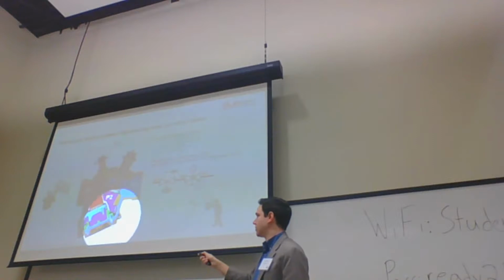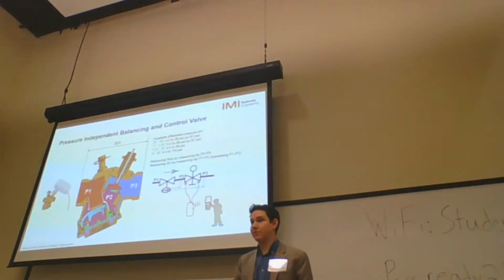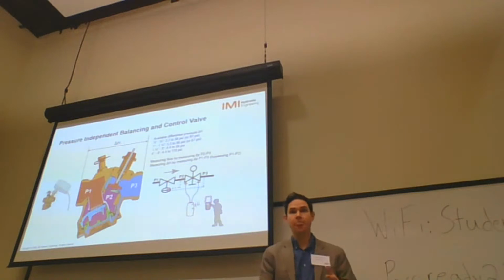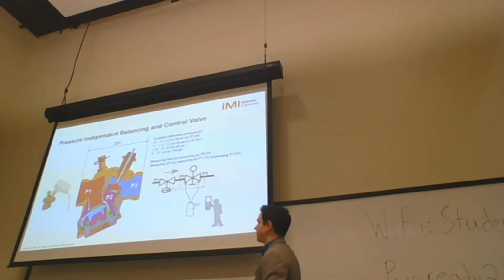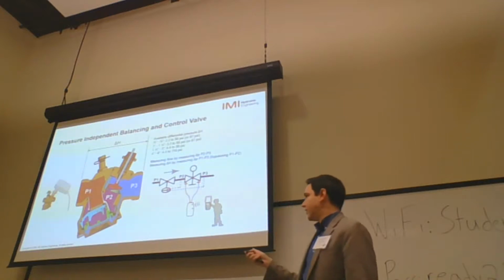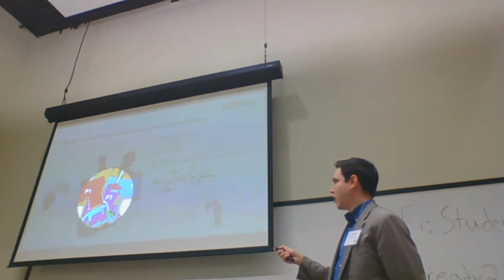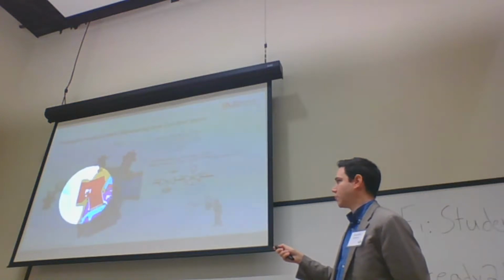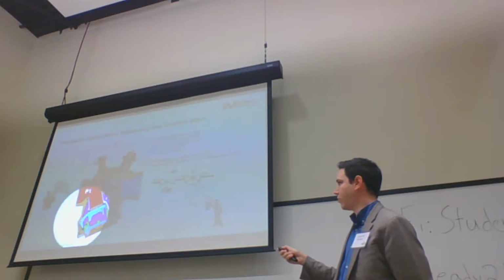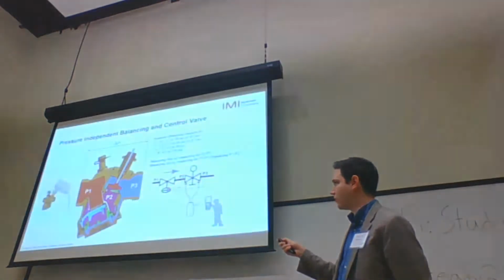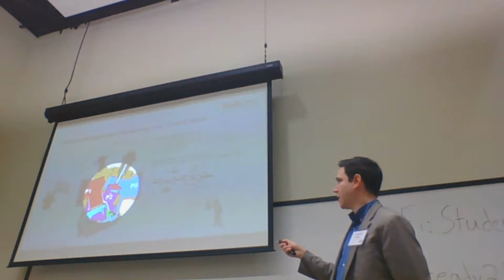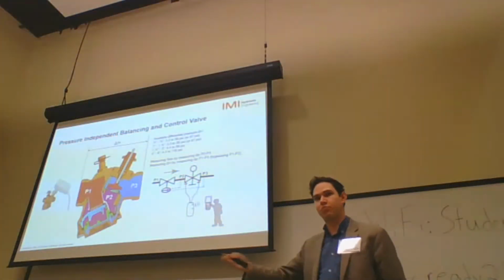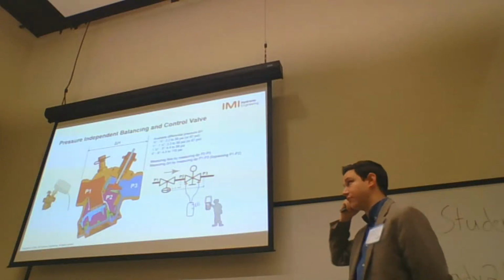So this black part right there, that is a membrane. And these white dots, that is the spring. It's exactly the same construction of a differential pressure controller. The only thing is that it's combining everything on the same body. So when you look at this pressure independent control valve, you have the P1, P2, and P3. P1 is the pressure before the differential pressure controller. P2 is the pressure after the differential pressure controller, this purple water, and also before the control valve, the balancing and control valve seat. And P3 is the third pressure outside of the valve, the outlet of the valve.